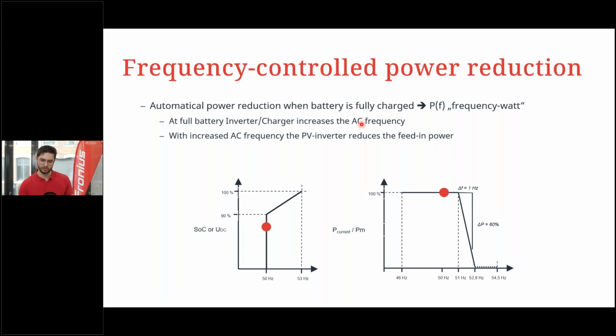And I can show you here on the screen how this looks like. By increasing the frequency, or this would be state of charge here, state of charge between 90 and 100%. And here on the bottom, we can see frequency from 50 to 53 Hertz. And in this range, it would then slowly but steadily increase it. And by that increase, the inverter knows, okay, at 51 Hertz, I need to regulate down and down and down until we have 100% state of charge, and I need to shut down completely.